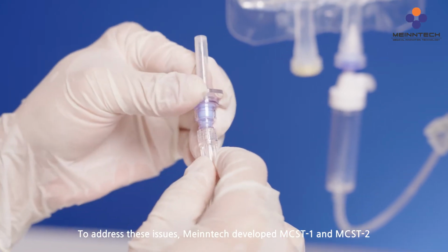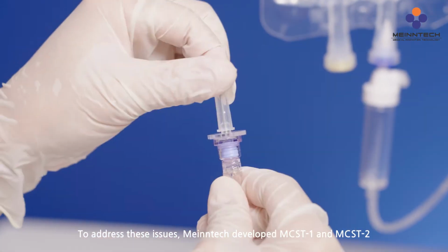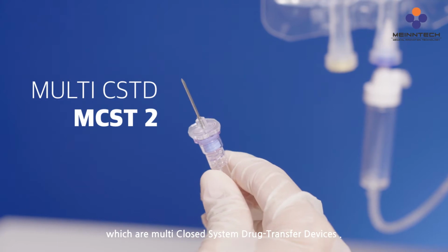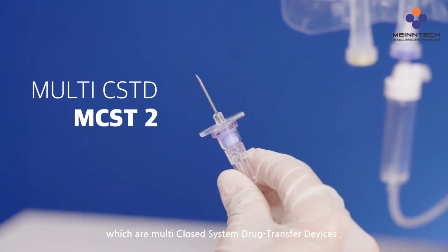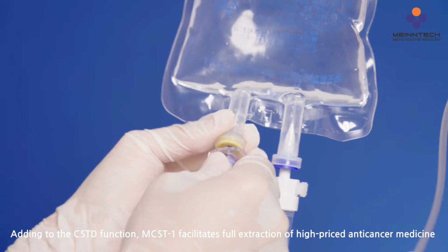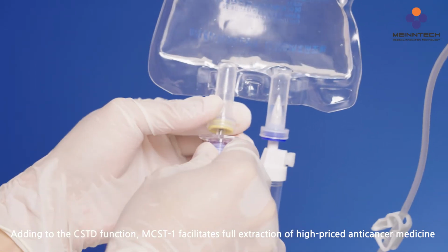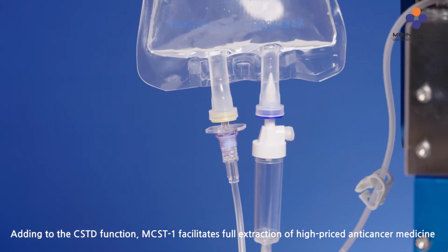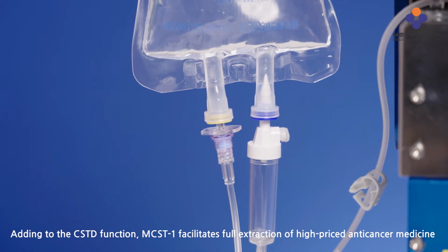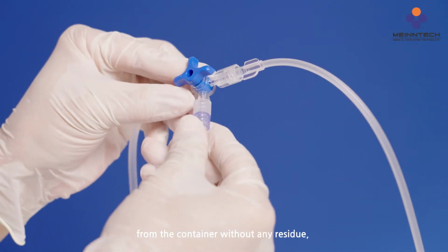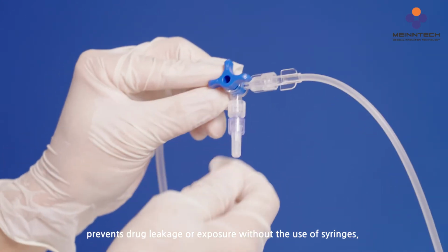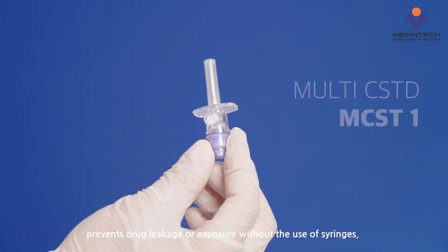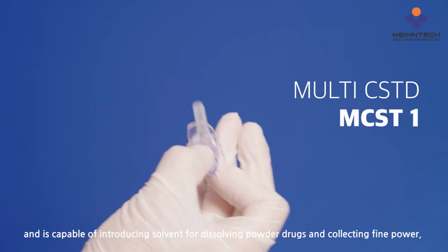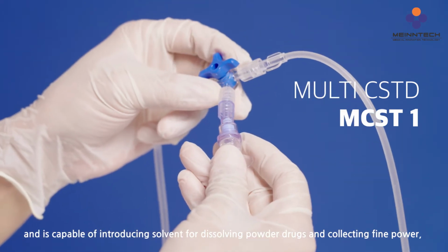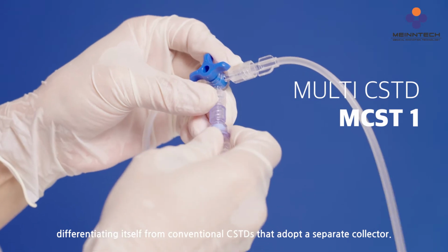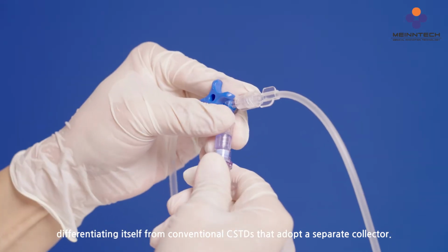To address these issues, Meinntech developed MCST1 and MCST2, which are multi-closed system drug transfer devices. Adding to the CSTD function, MCST1 facilitates full extraction of high-priced anti-cancer medicine from the container without any residue, prevents drug leakage or exposure without the use of syringes, and is capable of introducing solvents for dissolving powder drugs and collecting fine powder, differentiating itself from conventional CSTDs that adopt a separate collector.